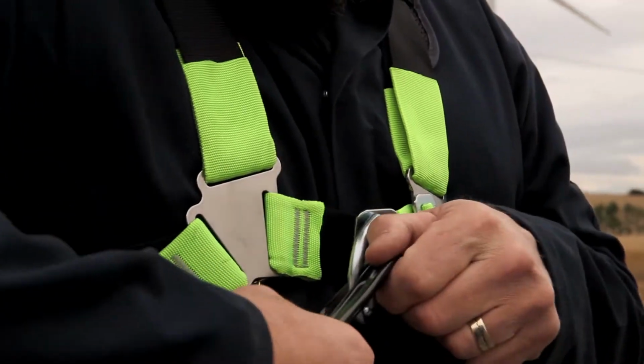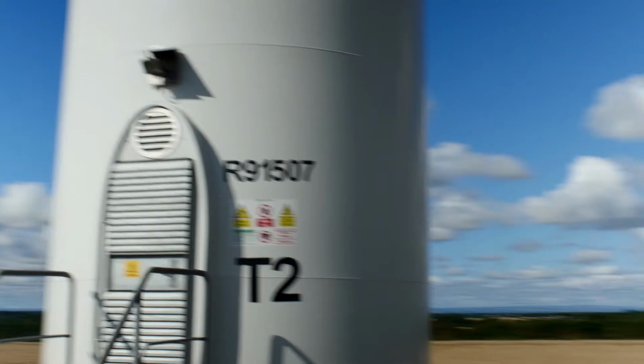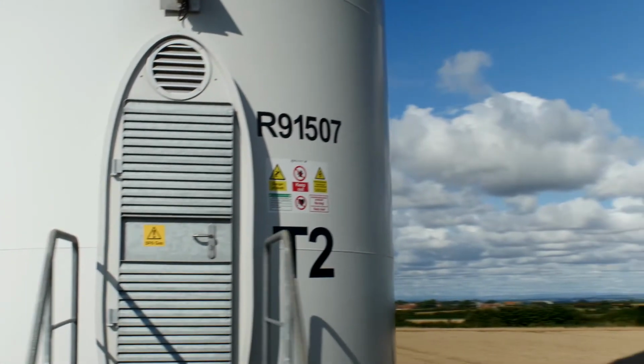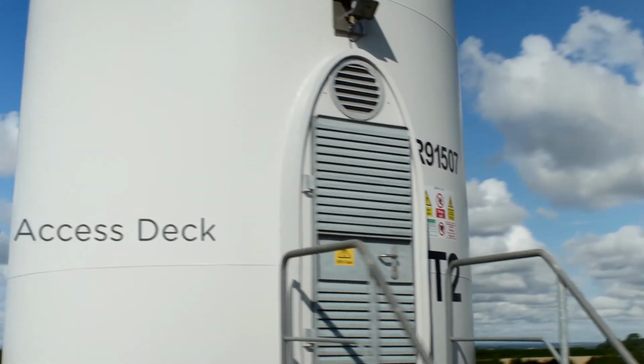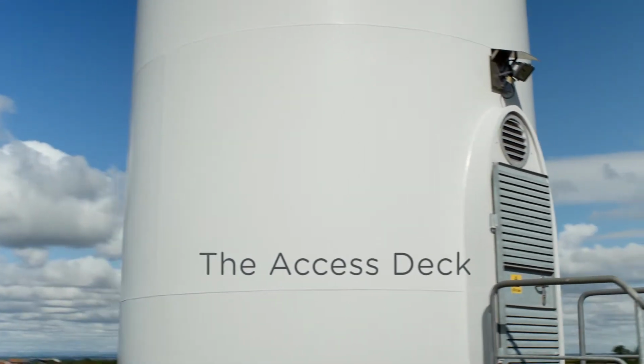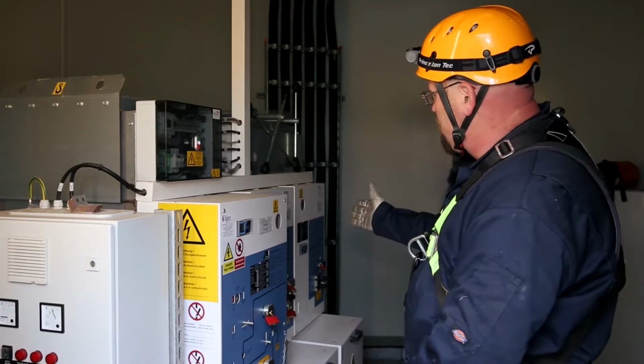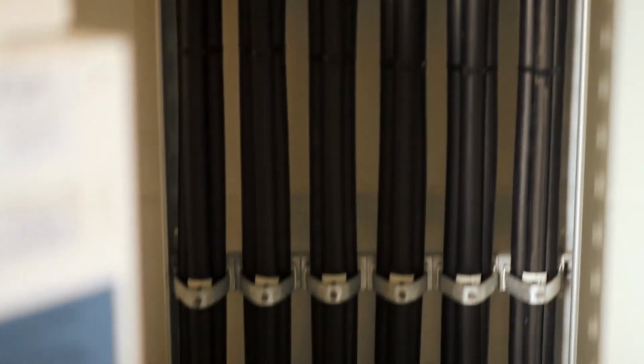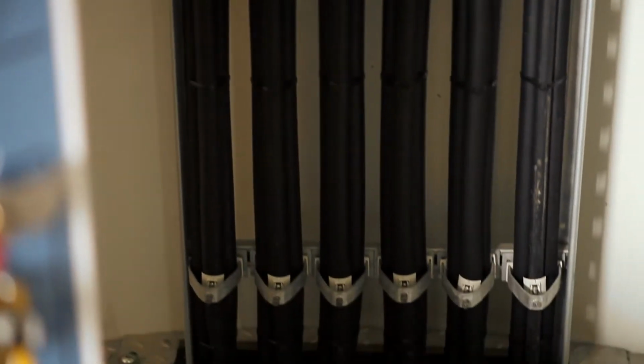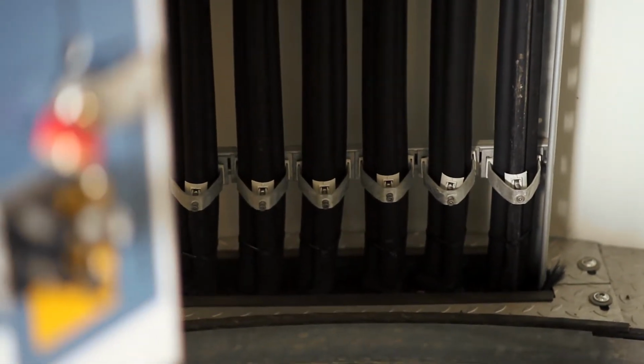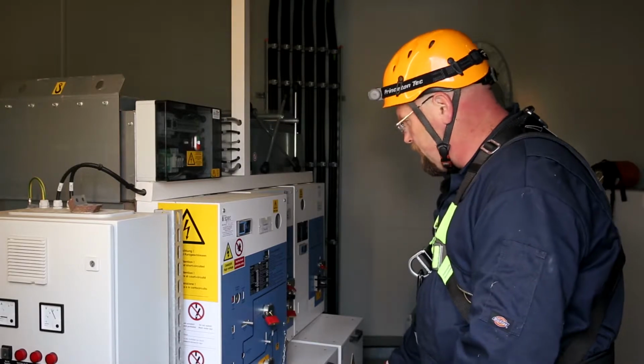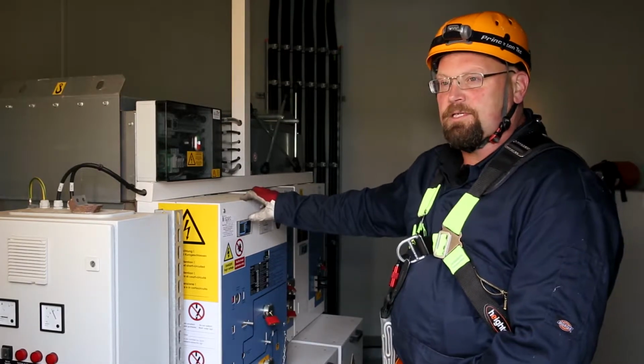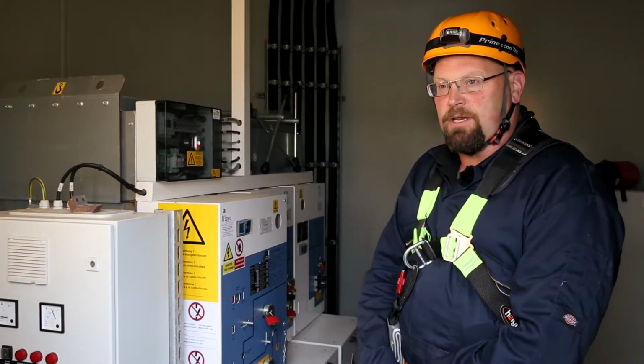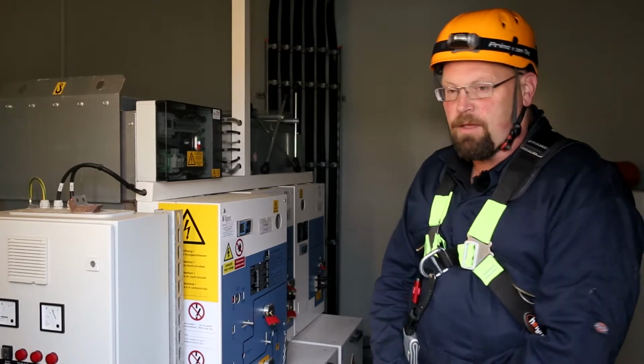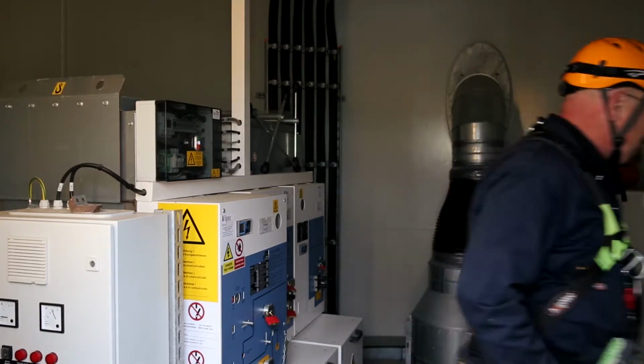Each turbine on the site is checked monthly. The engineers enter the turbine on the access deck. We're at the access level of the turbine now. Inside here we have high voltage switchgear. We have large cables coming down from the generator upstairs. It generates at 690 volts. That goes into a transformer on the deck below me here, and then into the high voltage switchgear and out for distribution onto the network at 33 kV. Okay, I'm going to head upstairs now.